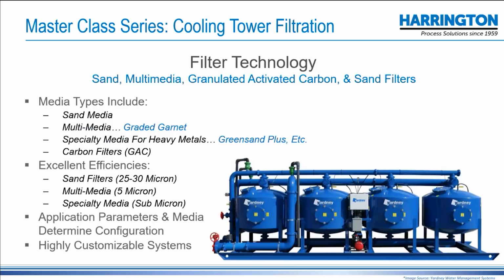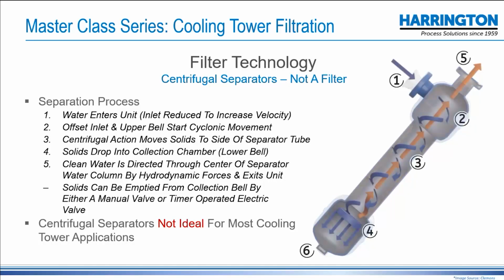And then media filters. Far too much to talk about here, but sand media would be very popular for cooling towers. That was one of the previous images I showed, a skid with a sand media filter on it. Carbon filters, specialty media for heavy metal removal. If you had a specialty media like a Green Sand Plus filter, it would be a taller filter than what you see here, but it would filter down into the sub-micron range if the water chemistry is right. But that's really not the concern. It's there more for iron, manganese, and other heavy metals. Now, none of those will do anything about scalant or corrosive, scalant-causing components like silica, magnesium, calcium. Even a media filter is going to have virtually no effect on that.